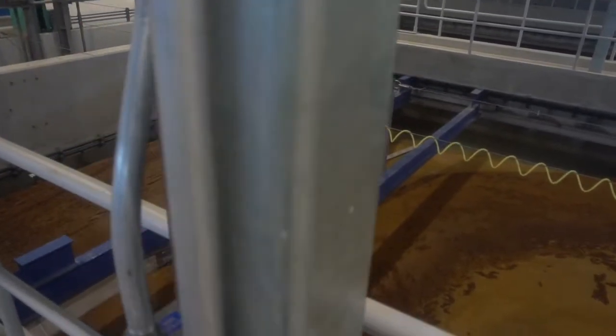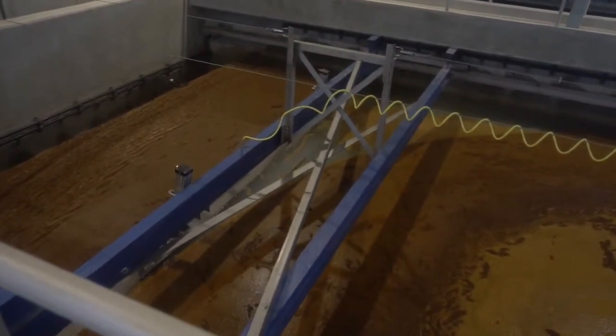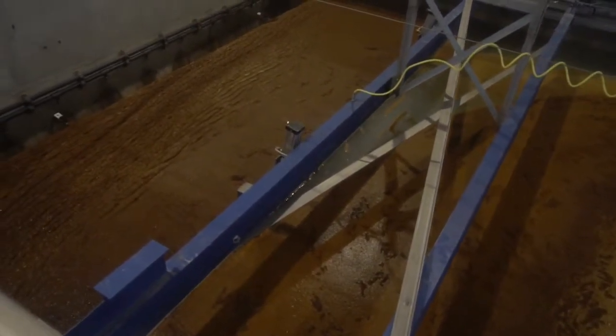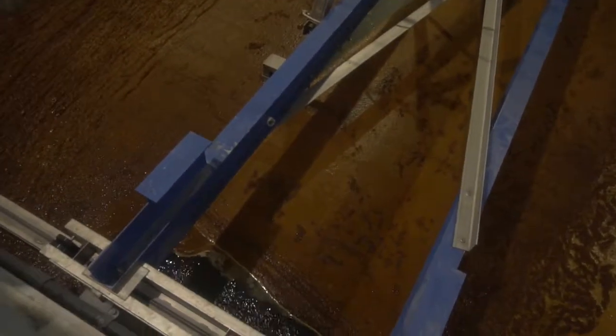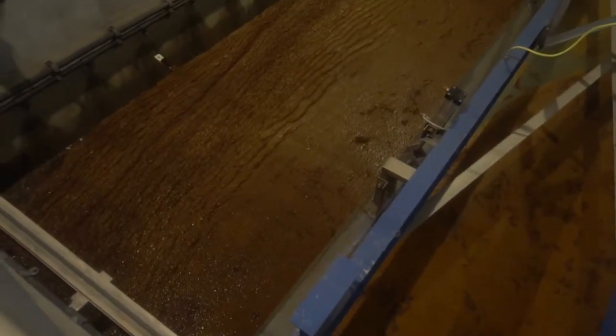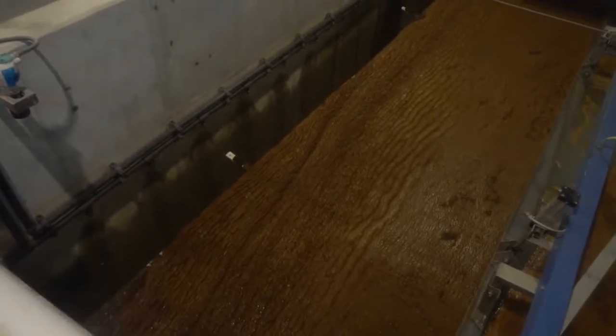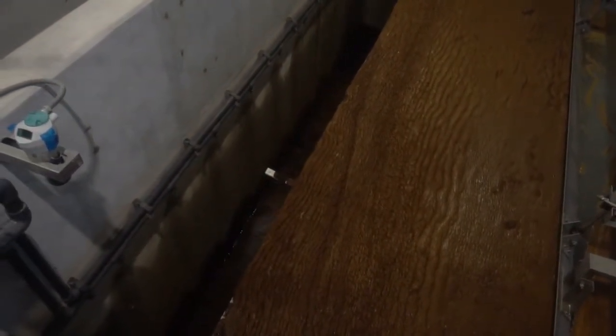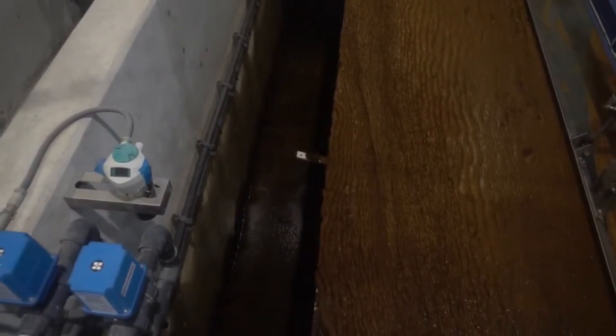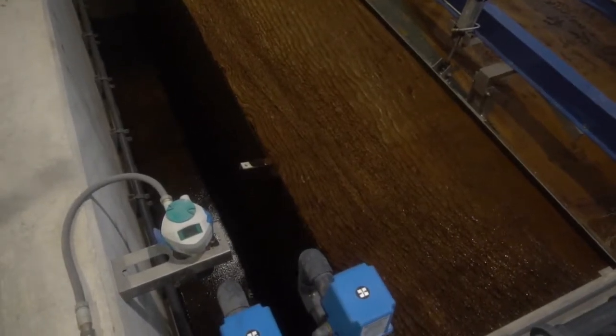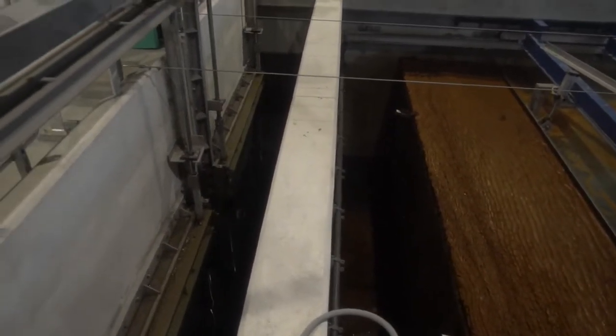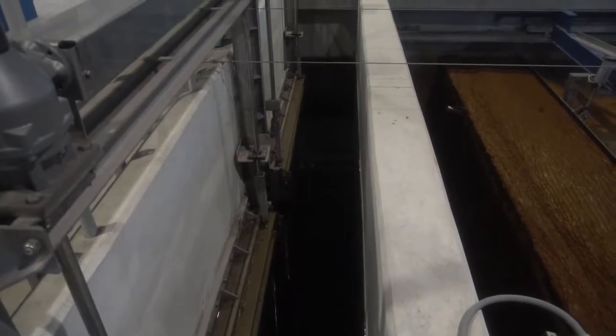These residuals of trapped flocculant and particles suspended in the water are removed continuously through a device, the timing of which can be operator controlled, and then these residuals can be skimmed off and put into a residual channel. These residuals are brought to our residual lagoons for further treatment. The clean water then goes to an effluent channel and prepares for filtration, which is the next unit process. We have 3 of these DAF units, each one rated at 6 million gallons a day, so that with 1 unit out, we are still able to meet the required 12 million gallons a day.